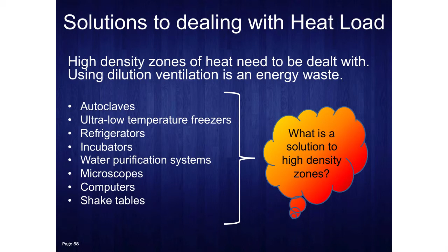So think about your mechanical system now. Was it oversized? Yeah, probably. Are you pumping way more air than is required to satisfy this space? Yeah. And how are you making up for that? How is that room not 55 to 60 degrees? Well, you're adding reheat. So there are certain spaces, and we showed those, that 5 to 9% of the space where you do have heating issues, and you have to be able to deal with that.